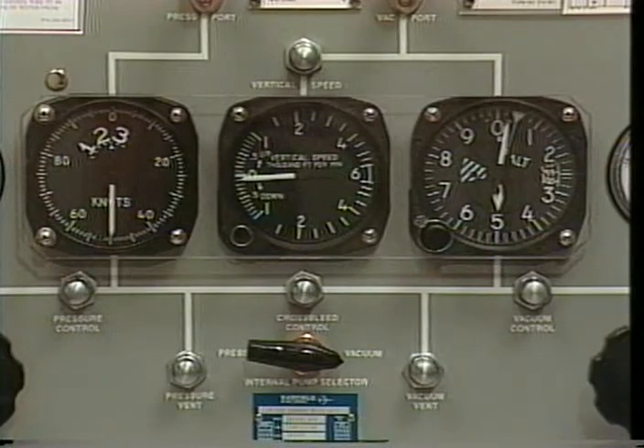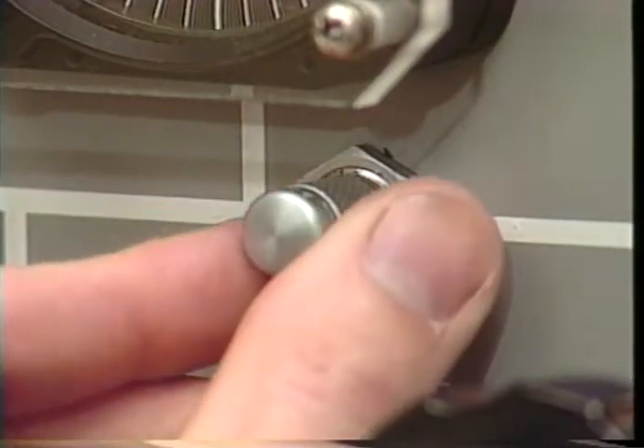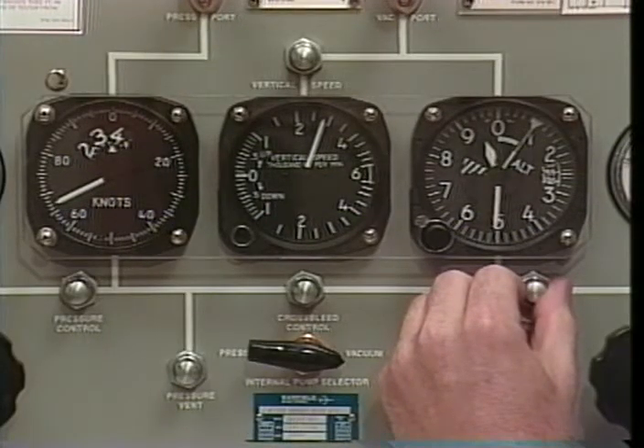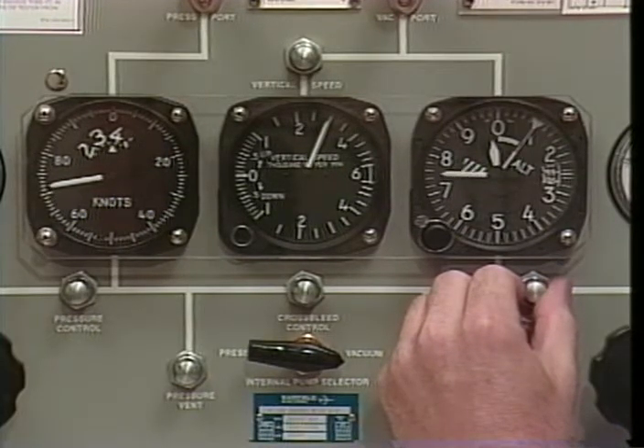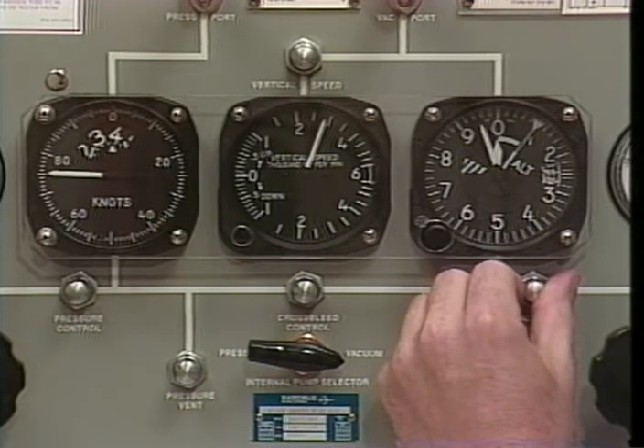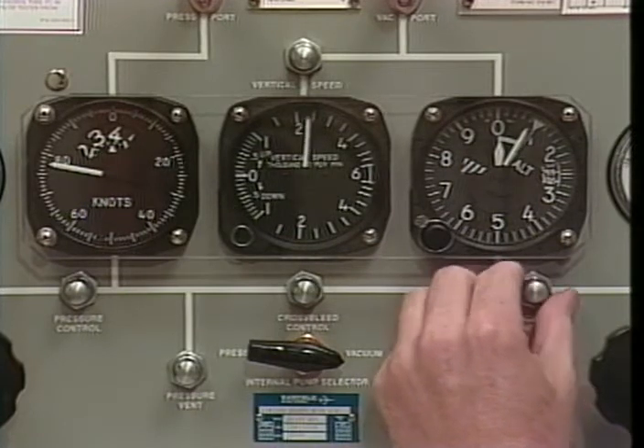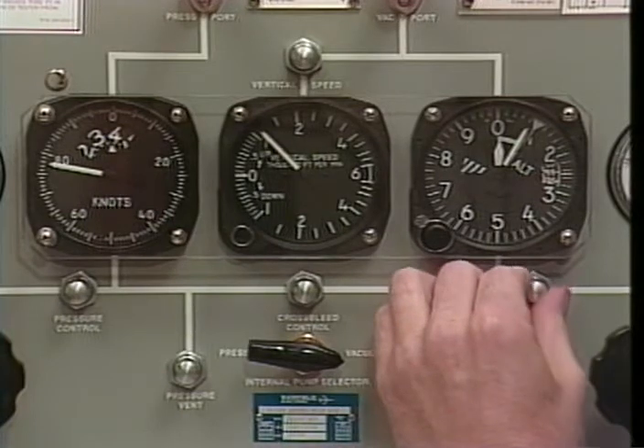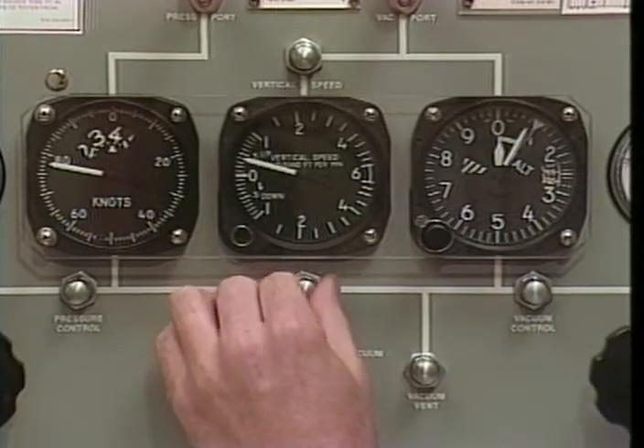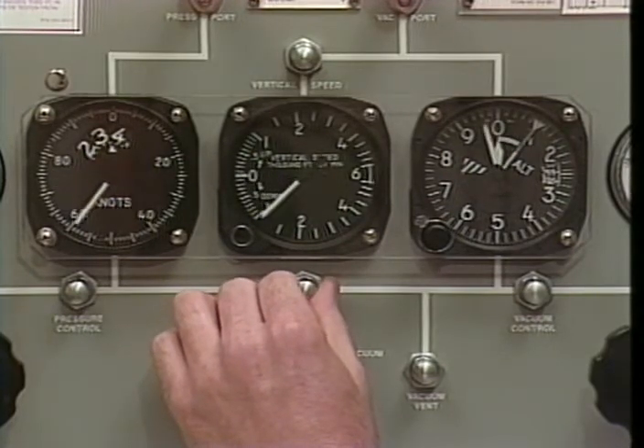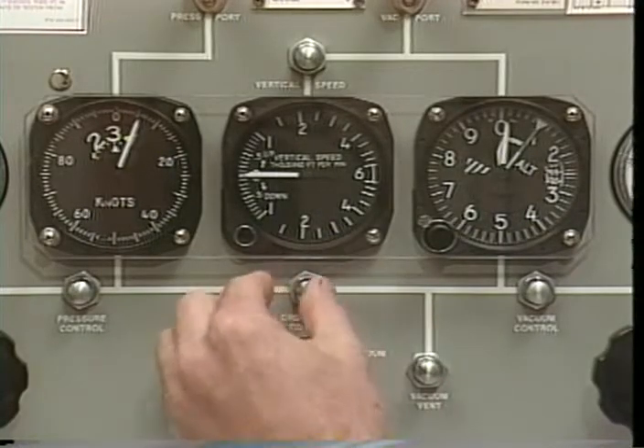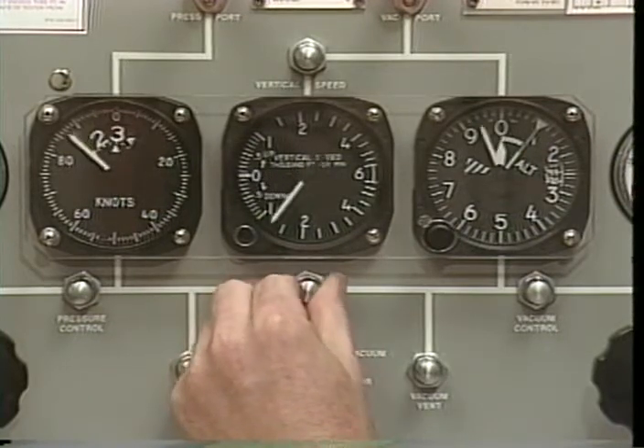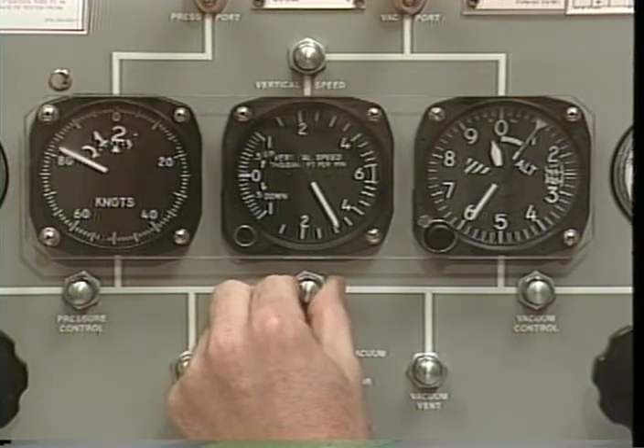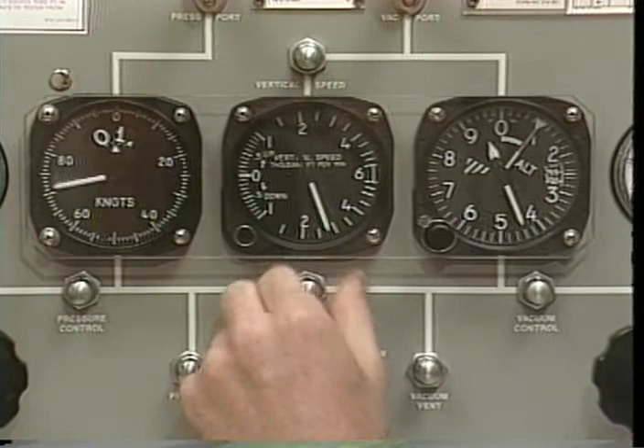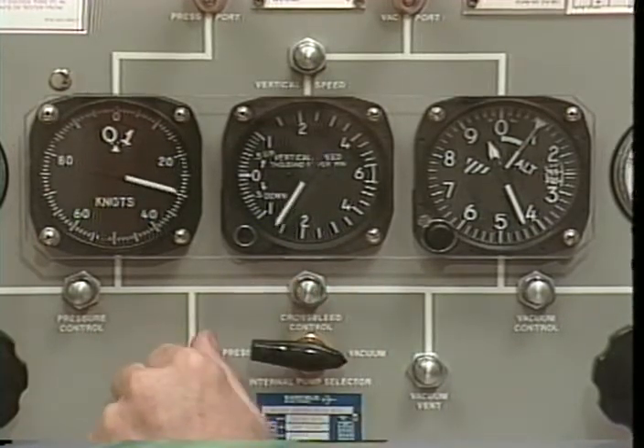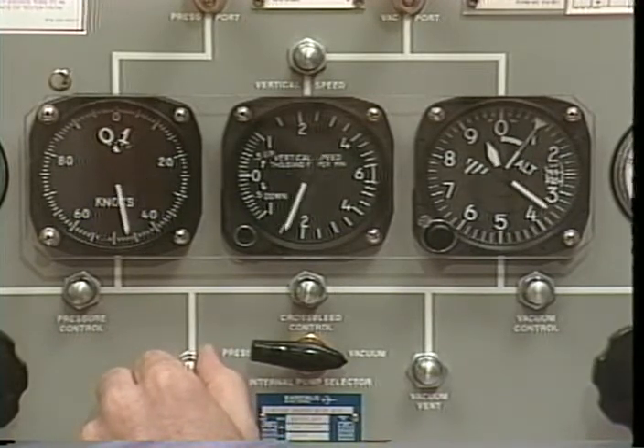With the first test point achieved, open the vacuum control to increase the vacuum in the static system and drive the altimeter to its next test point, 300 knots at 10,000 feet. Now look at the airspeed indicator. If you need to decrease the airspeed to arrive at 300 knots, open the cross-bleed valve. To increase the airspeed, open the pressure control valve. After you evaluate all the test points, open the cross-bleed valve to return the airspeed to rest. Then open the pressure vent and return the system to ambient pressure.